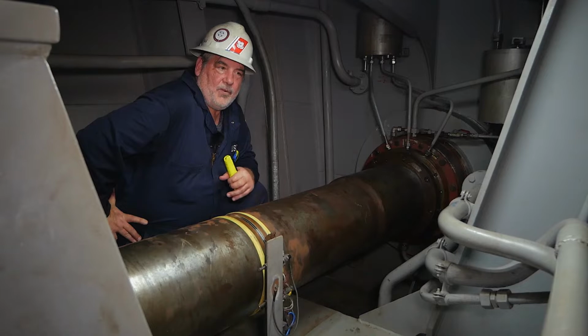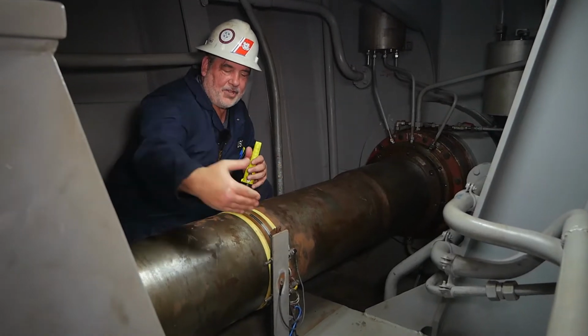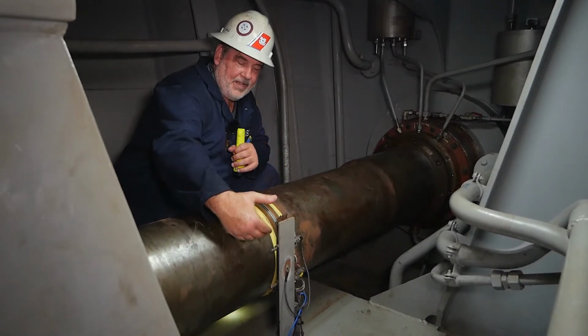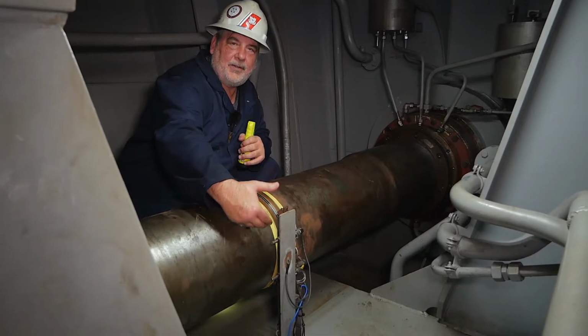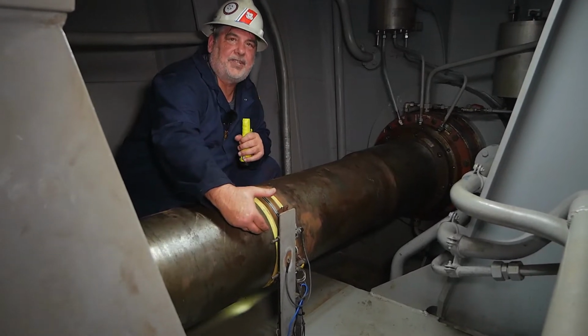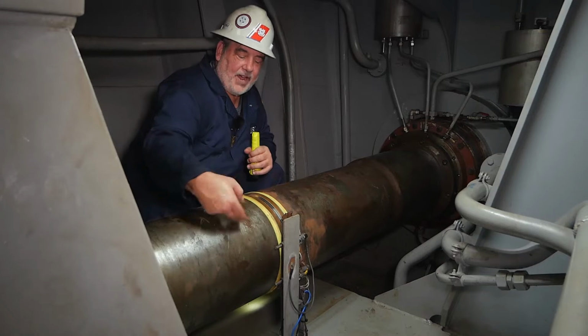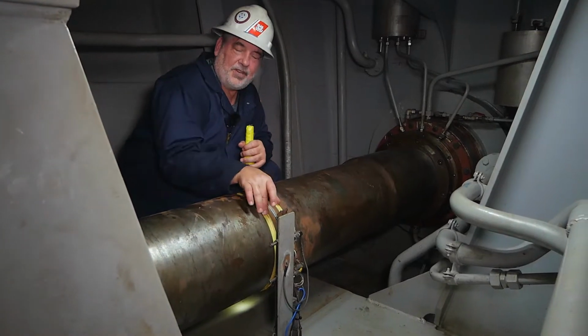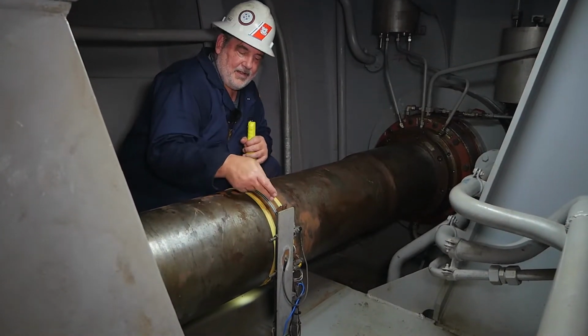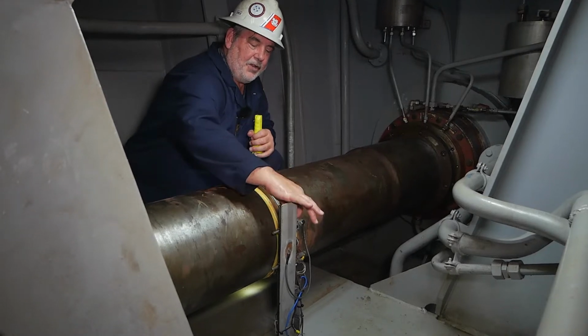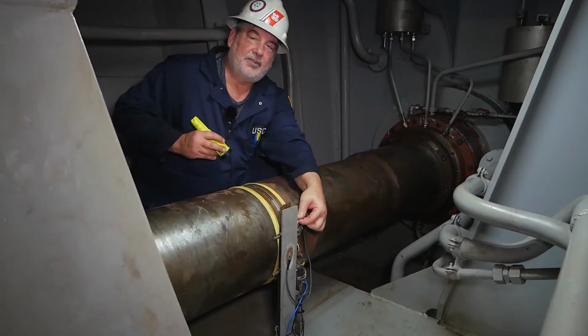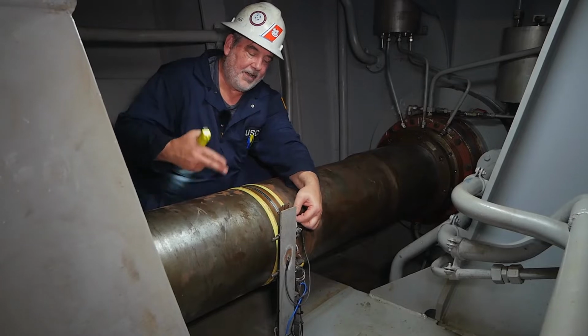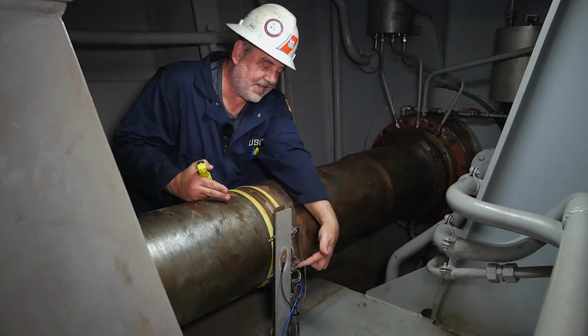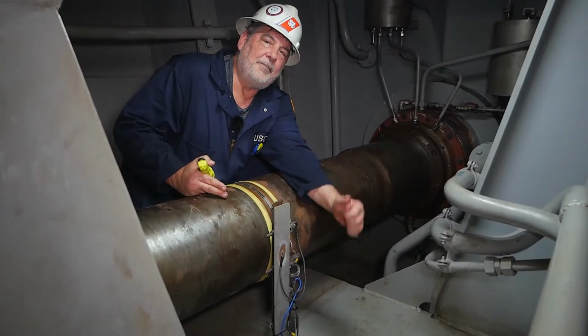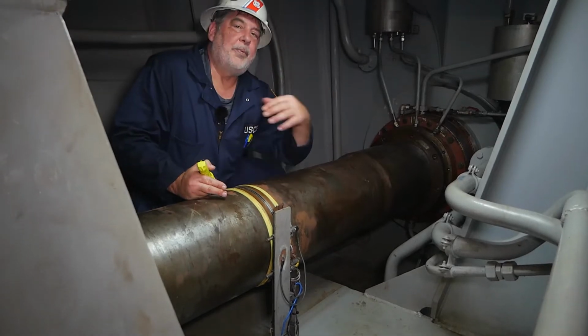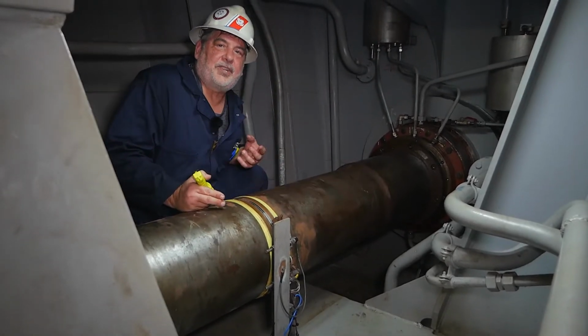Okay, what we have here is the shaft grounding system. This is a component within the cathodic protection system. As the shaft rotates, this is a silver band, and through silver and the use of brushes, like on a traditional motor, as the shaft spins, this thing is continually bonded to ground to prevent the buildup of electricity and voltages.